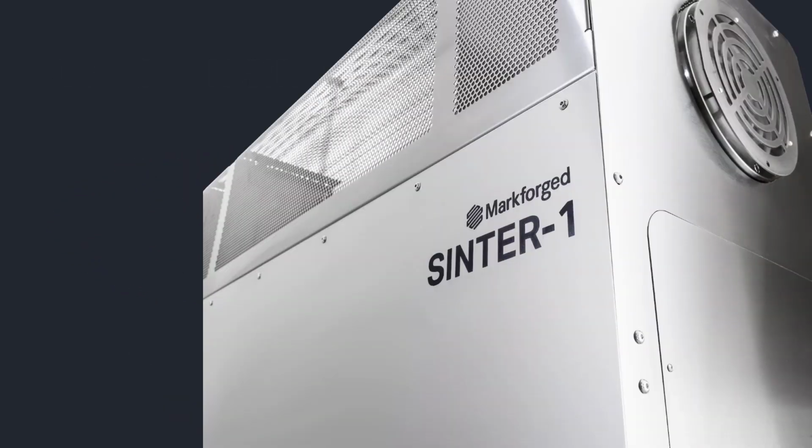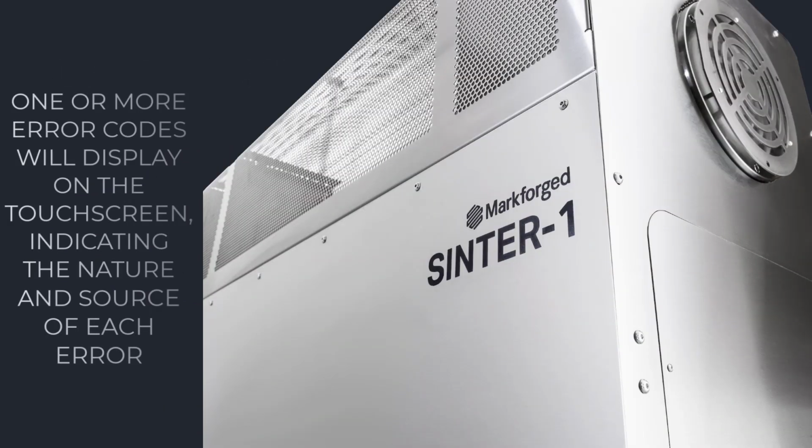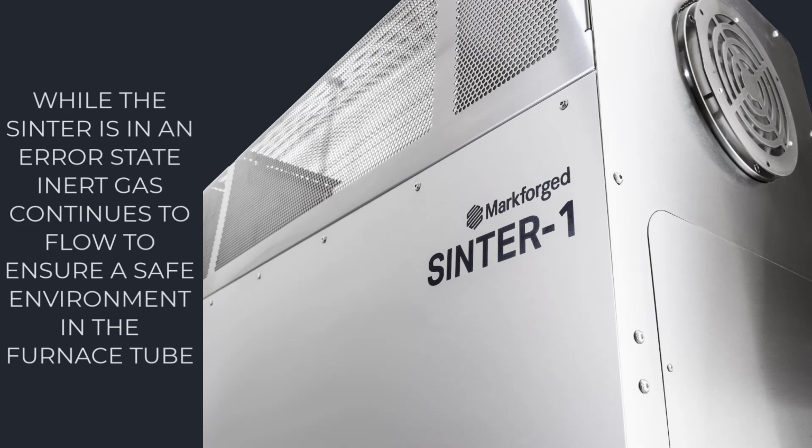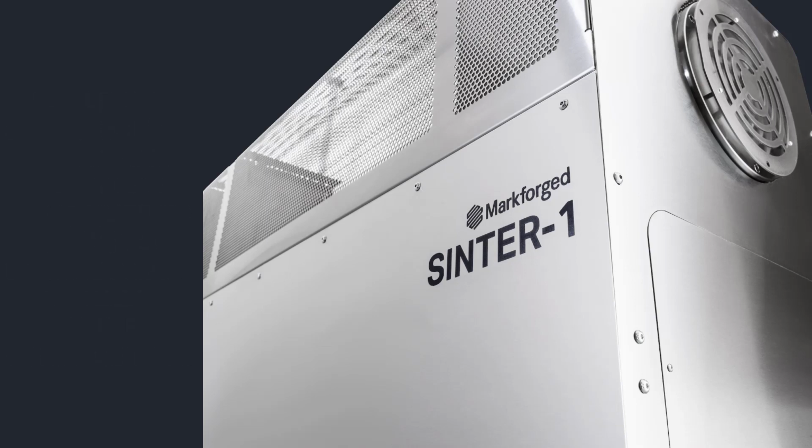In the case of a Sinter-1 firmware error, one or more error codes will display on the touchscreen, indicating the nature and source of each error. I would like to note that while the Sinter is in an error state, the inert gas continues to flow to ensure a safe environment inside the furnace tube.